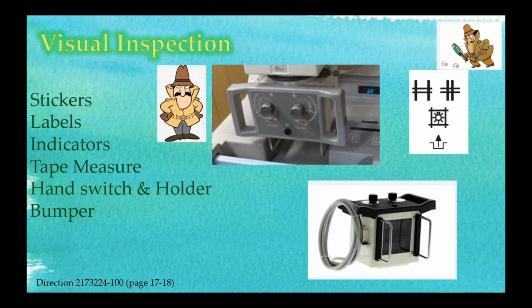Collimator light. We have what we know as a field light. The field light's very important because before I make the x-ray, I turn on the light and it's going to superimpose a light beam to where my x-ray is going to be. So you can imagine that has to be accurately symbolic of where the radiation is going to be. So that's another test that we do.